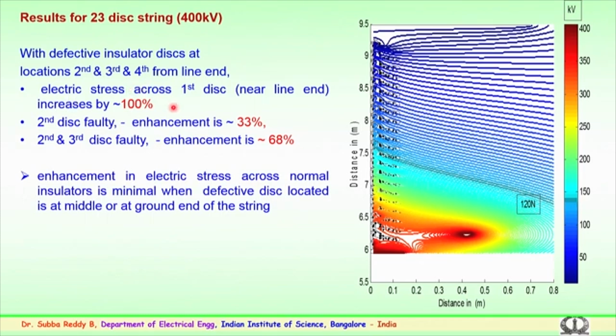So, the electric stress across the first disc, which is a good insulator very near to the conductor end. You can see the rise in electric stress is 100%, double the stress which it was facing when all the insulators were in service. Similarly, in case the second is faulty from the line end, the enhancement will be 33% across the first disc. For second and third, the enhancement will be 68%.